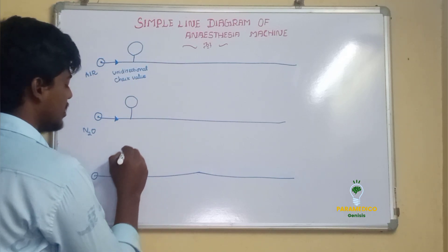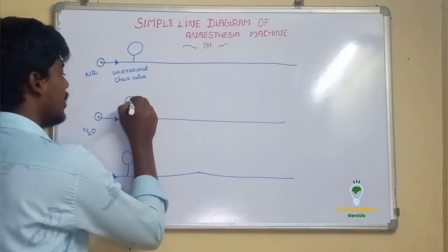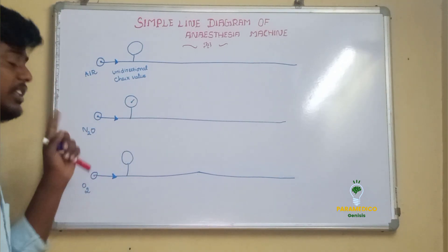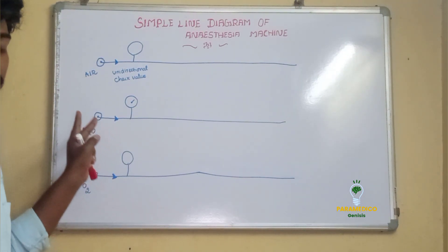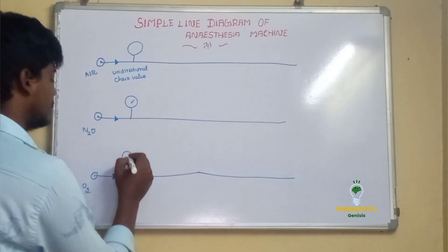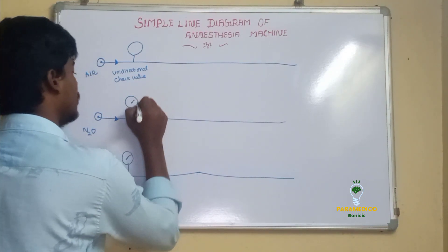After the unidirectional check valve, there is a pressure gauge. The pressure gauge shows what pressure is present in the cylinders — for example, the oxygen pressure in the cylinder. It simply displays the current pressure of the medical gas cylinders.